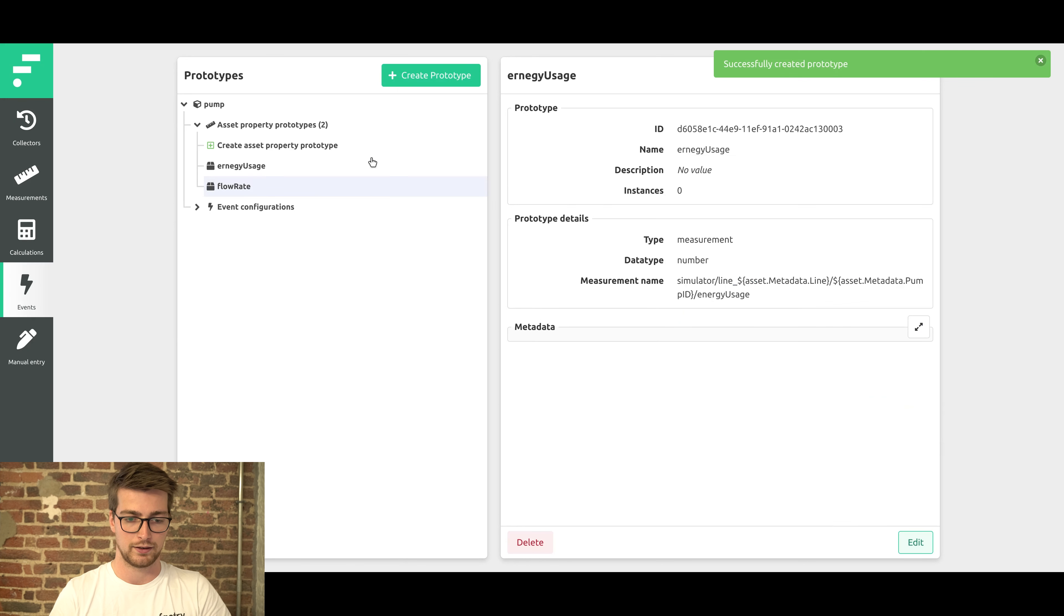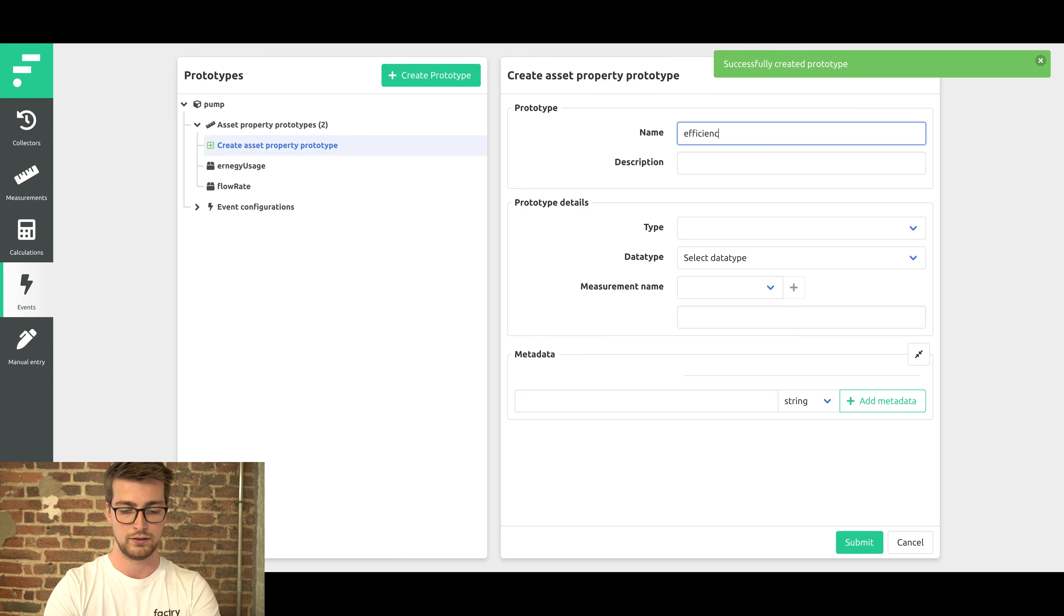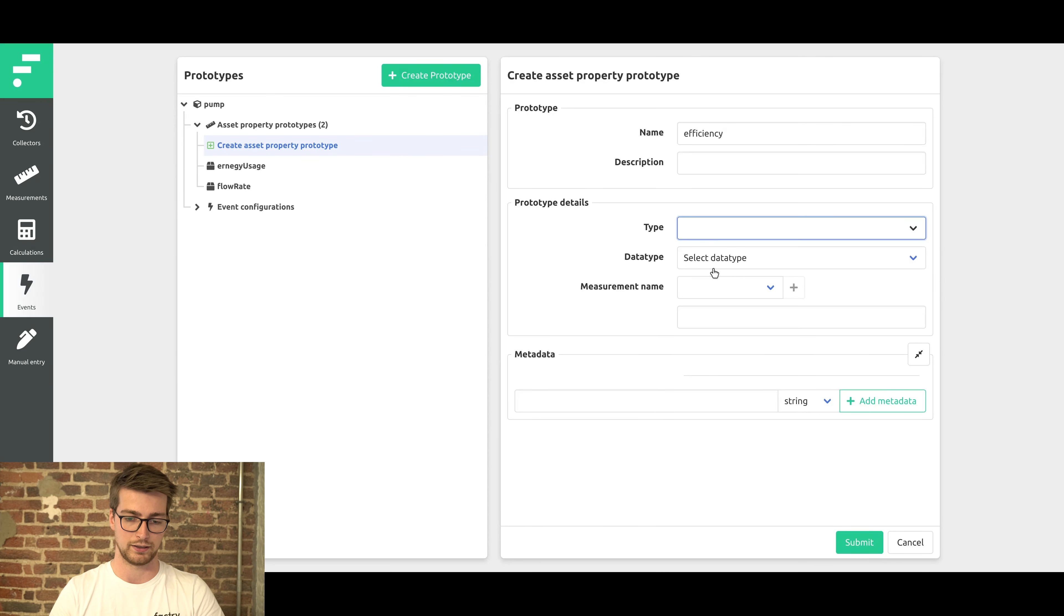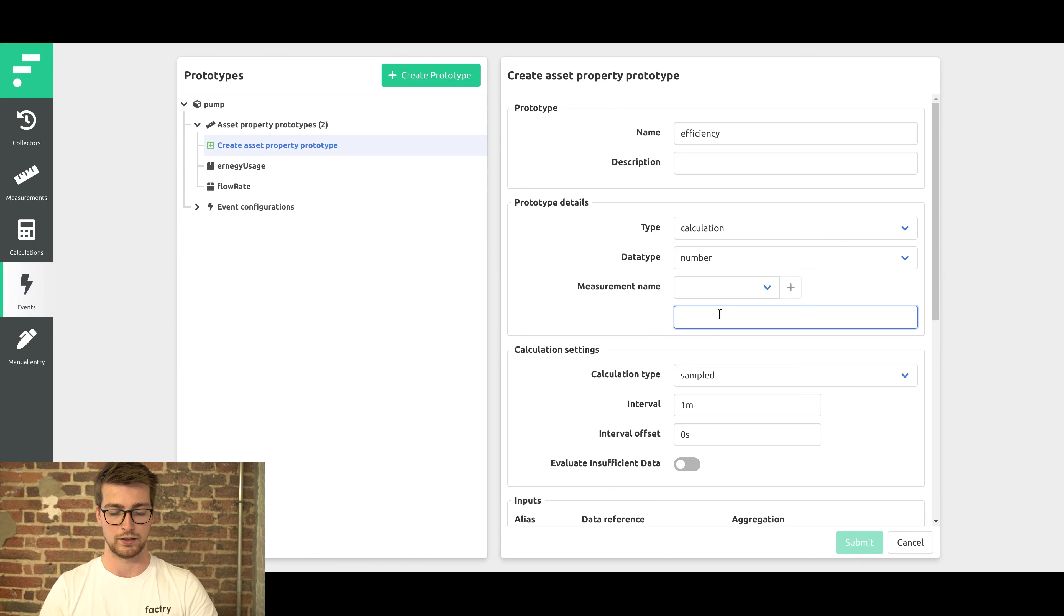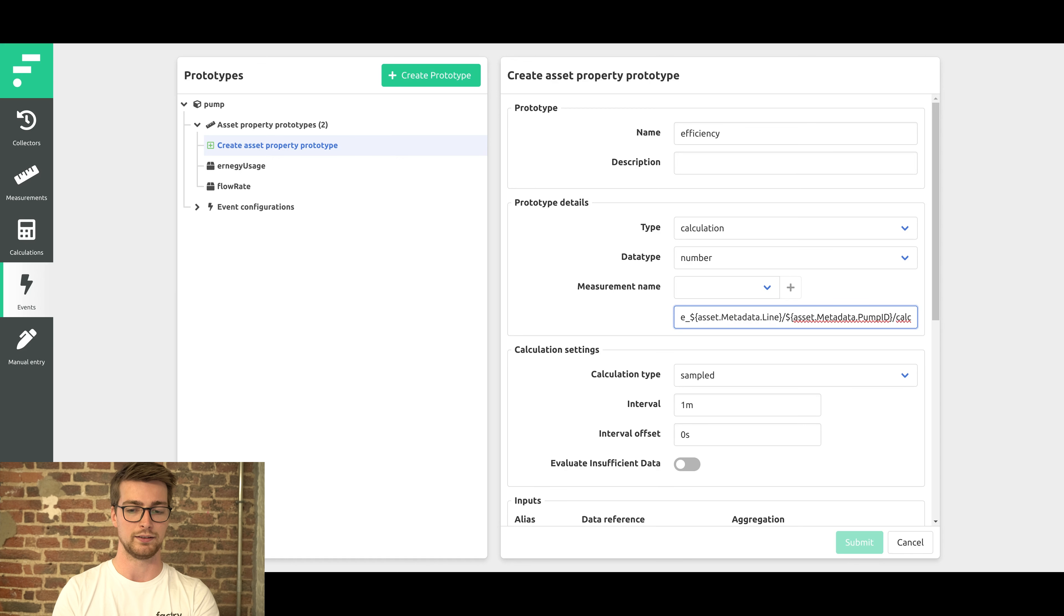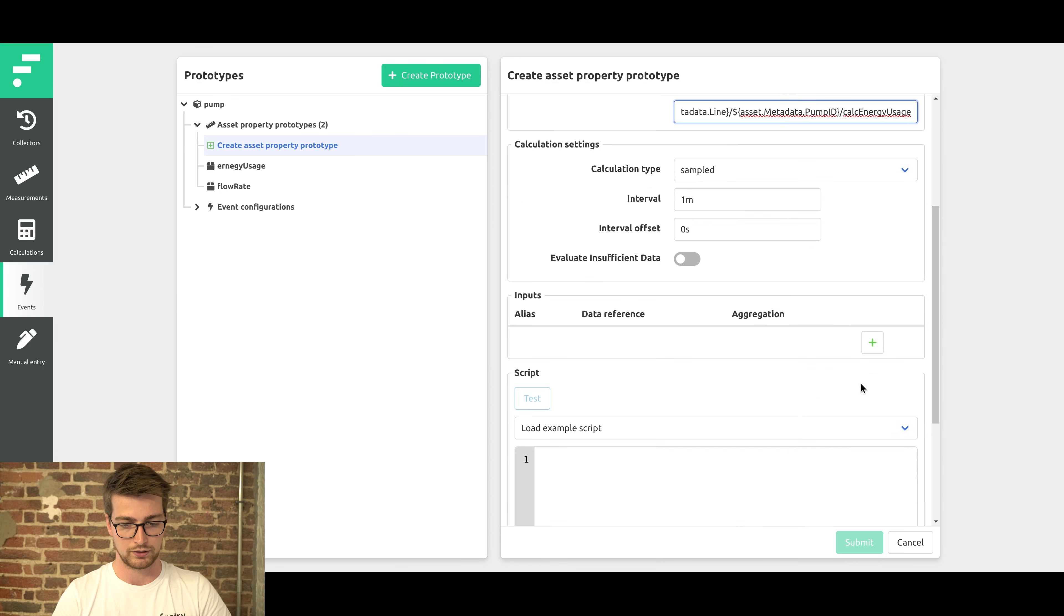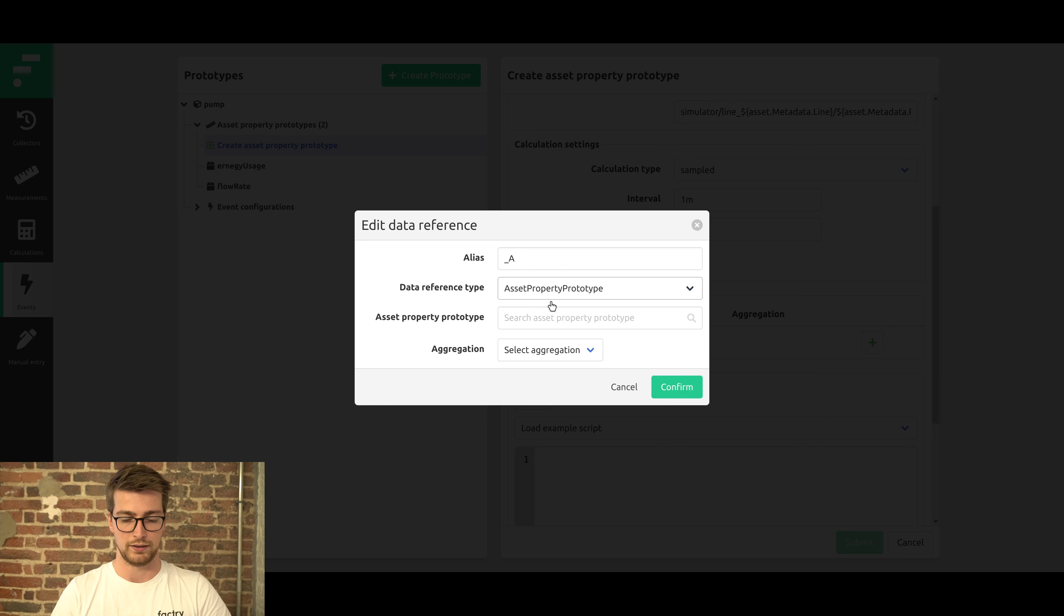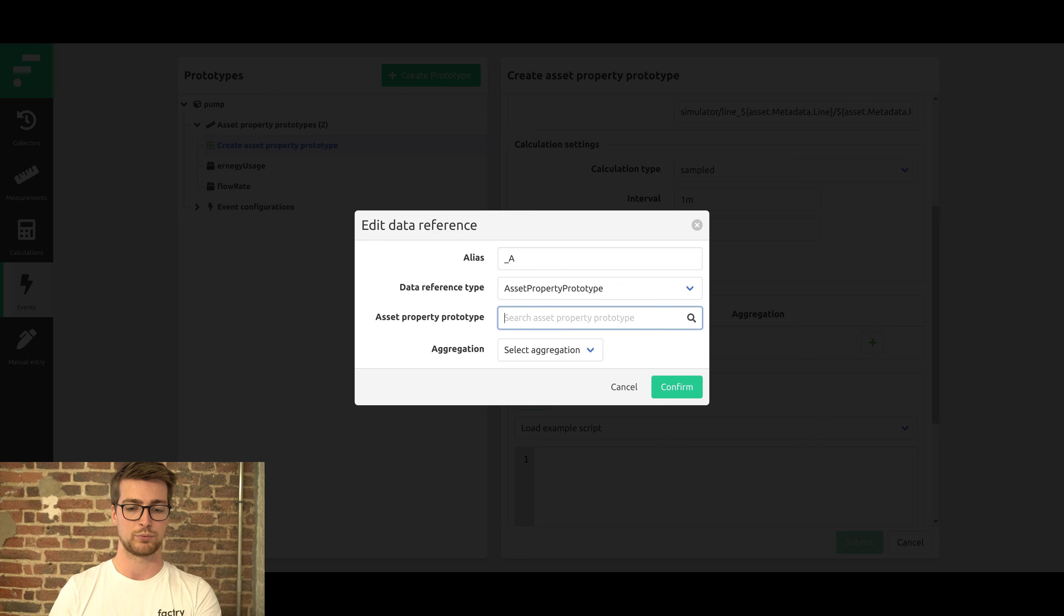But lastly we're going to also add the efficiency. This will be a calculation using the energy usage and flow rate. So we select calculation. The result will be a number. Then we template the name for this calculation. This does not reference an existing calculation; this will be the name of the calculation that will be created. Then we configure the calculation as we already know, with the added benefit that we can reference the configured asset property prototypes already here.